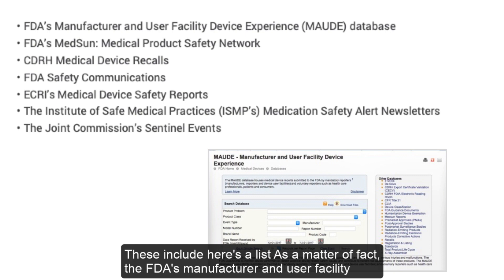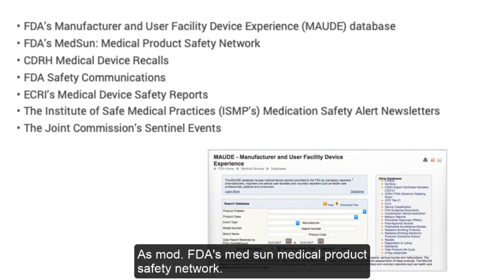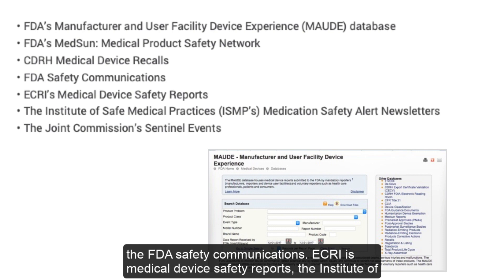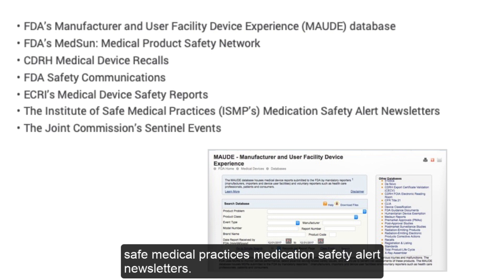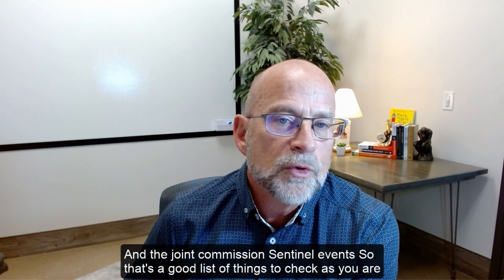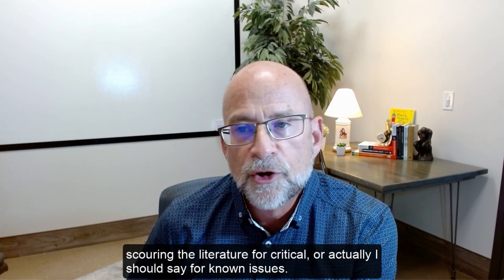The Human Factors Guidance also provides a list of other sources where these issues can be found. These include the FDA's Manufacturer and User Facility Device Experience Database (MAUDE), FDA's MedSun Medical Product Safety Network, CDRH's Medical Device Recalls, FDA Safety Communications, ECRI's Medical Device Safety Reports, the Institute for Safe Medical Practices Medication Safety Alert Newsletters, and the Joint Commission Sentinel Events. That's a good list of sources to check for known issues.